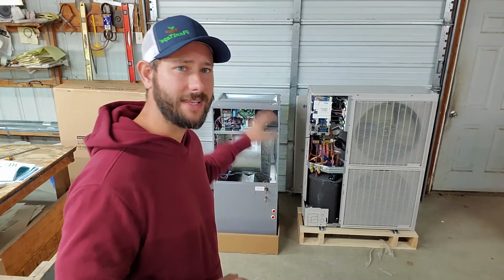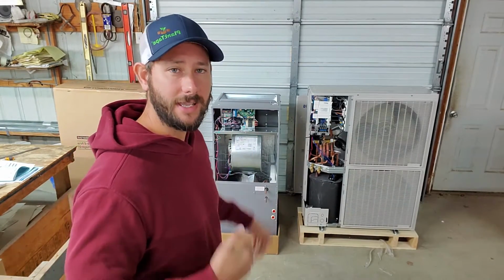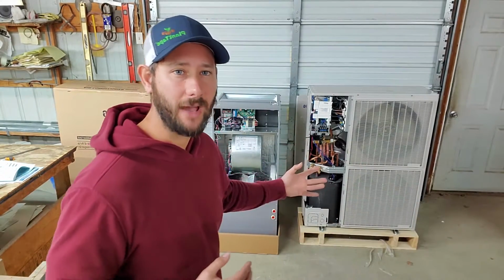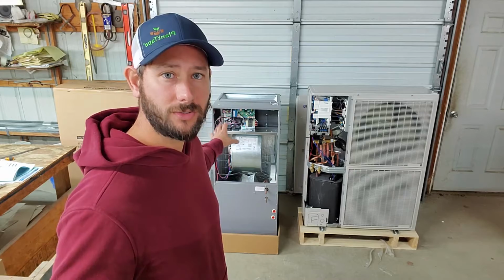Second thing I want to say is auxiliary heat strips. Heat strips are very inefficient, but when you need to hit a balance point, when it gets really cold outside and the load of your structure basically exceeds the capacity of the outdoor equipment, with conventional, you have to have heat strips. So your heat pump may take a 30 amp breaker, but your heat strips would take a 60 amp breaker. So they're very, very inefficient. You don't want to use heat strips.